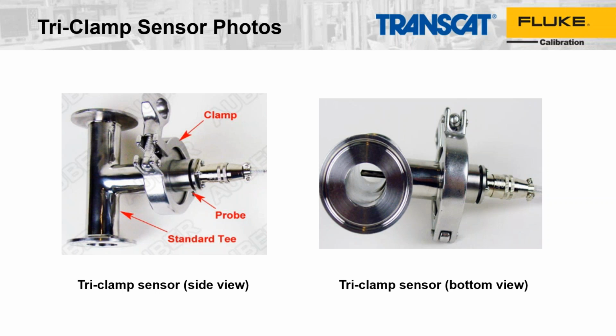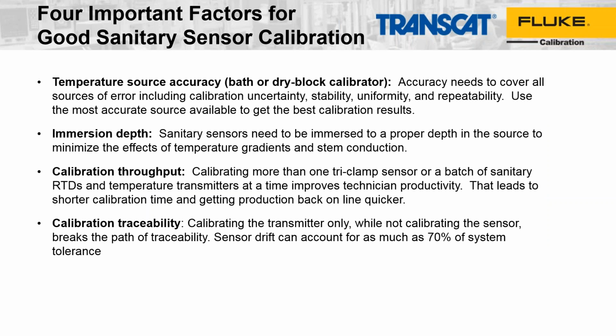So some important factors to consider when calibrating sanitary sensors or tri-clamp sensors is, first of all, consider the temperature source. And what we mean by temperature source is the tool that will provide the temperature set point needed for the calibration. And probably the main specification to consider is the overall accuracy of that device. Many of these temperature sources, like these baths or dry block calibrators, have a built-in display with an accuracy specification that hopefully covers all of the pertinent sources of error or sources of uncertainty, like stability, uniformity, repeatability, so that it makes your job a lot easier. You can use this comprehensive specification to know what to expect and to make sure you're using equipment that's adequate for the application.